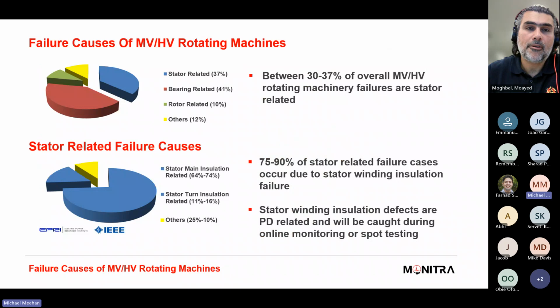To be honest, today I focused on the stator. Everything we've discussed, the stator related issues and all the PD related issues, is what we're focused on. The bearing is purely mechanical, whether it's a pedestal bearing or a white metal bearing. I'm not aware of picking up any PD activity from bearing related issues. I would say that would be vibration and maybe bearing temperature. So your condition monitoring of the bearings, in terms of vibration sensors and temperature sensors, is how that one is managed.